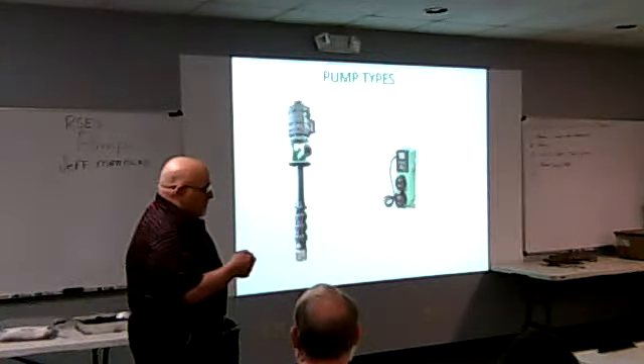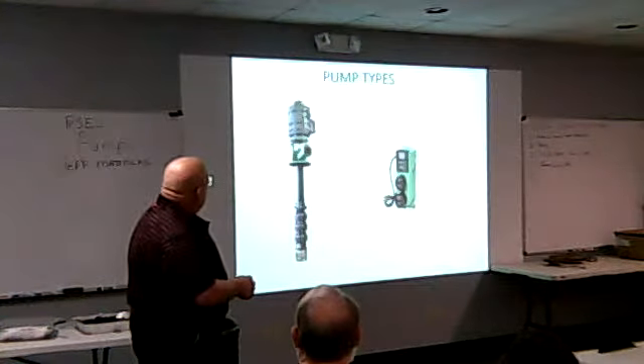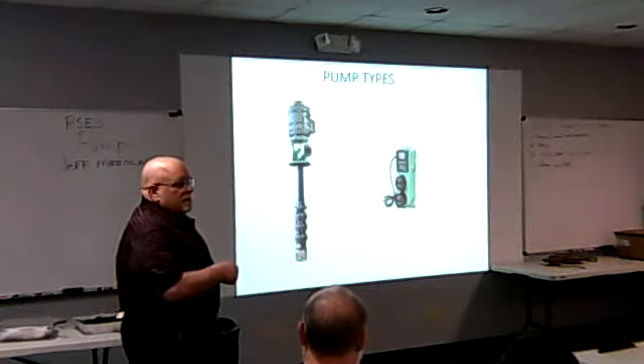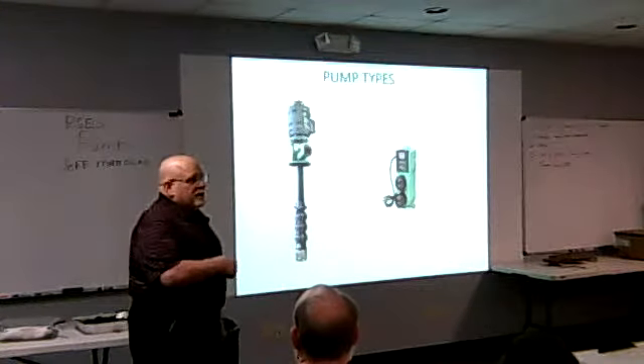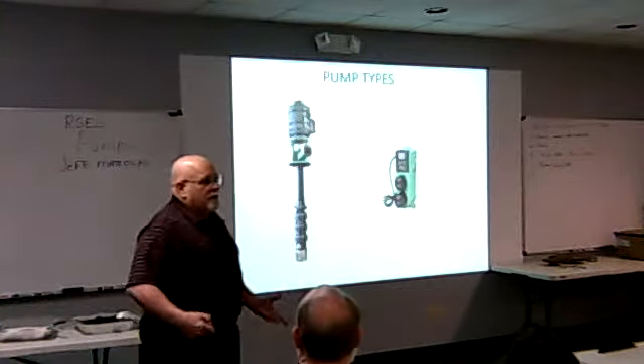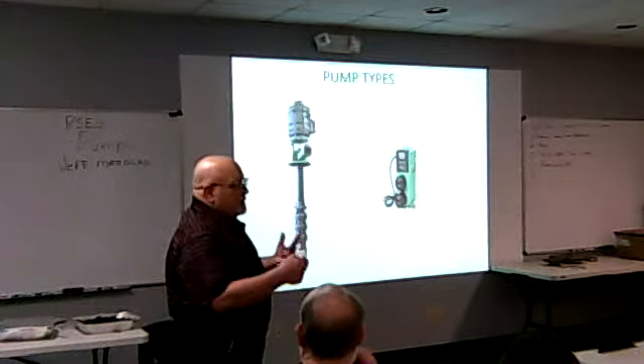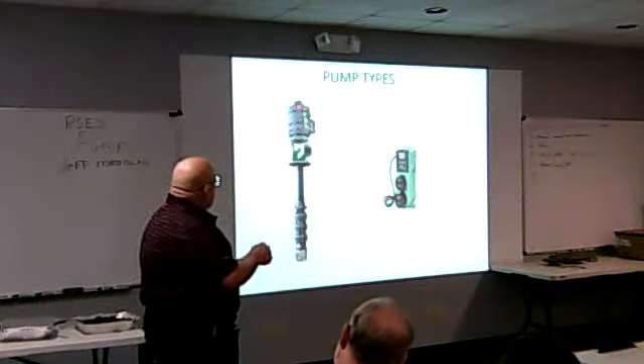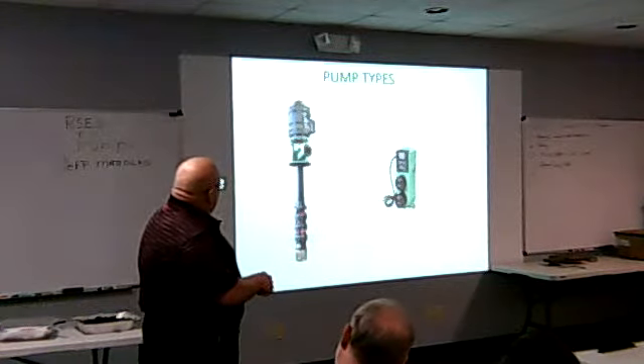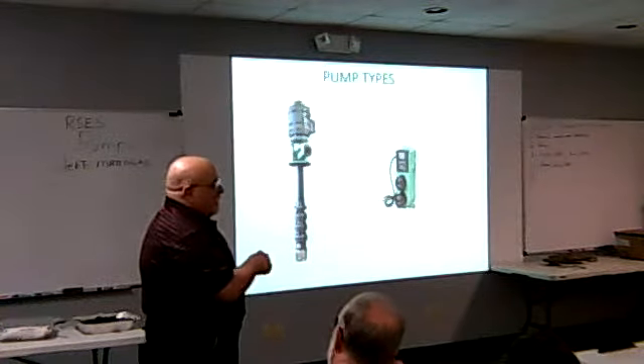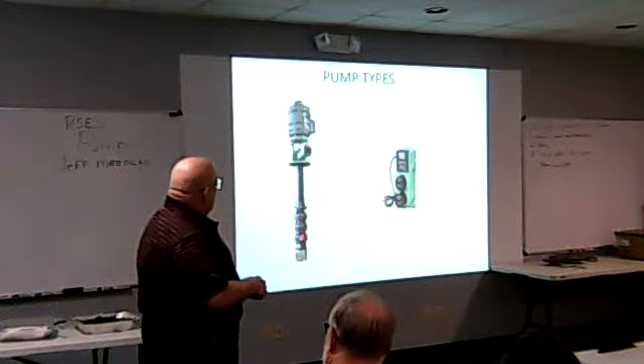This is a vertical turbine pump. The way these work, you would mount this on a base plate. This would actually hang down in the sump. These are used a lot on cooling towers. We've got a sump right underneath. The tower returns right back to the sump. This spins. The water, these are impellers. I can keep stacking these impellers. I can have a single, 2, 3.